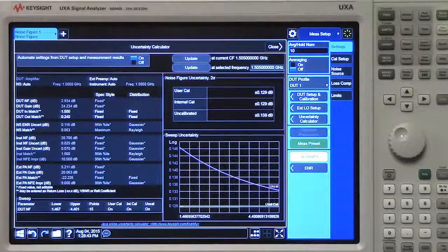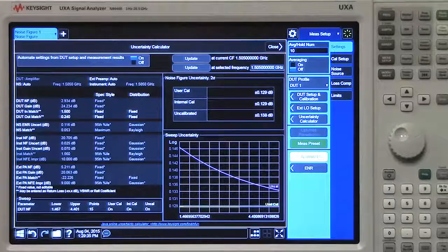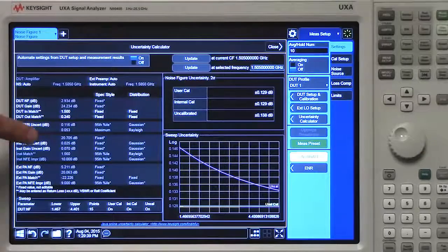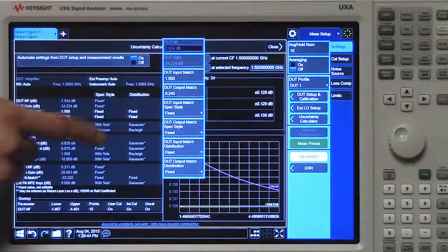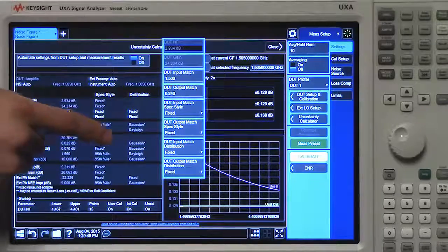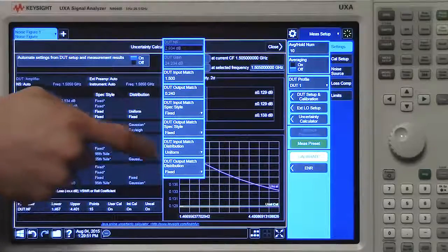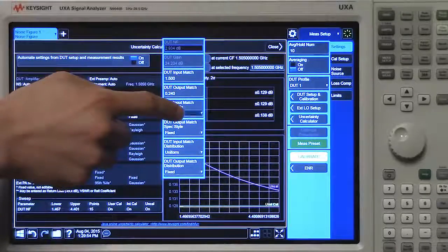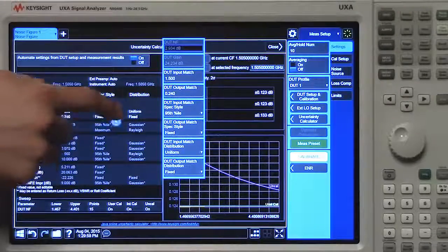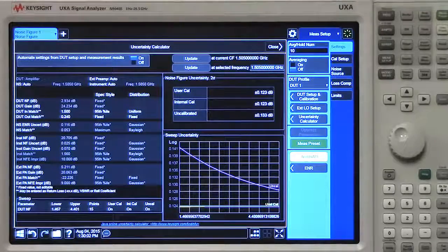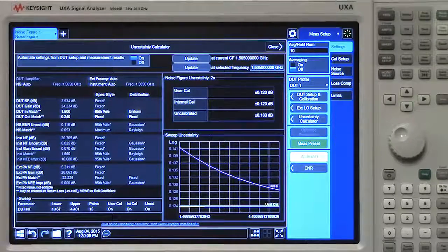Our competition, on the other hand, forces the user to manually enter these values. Also notice we give you full control over the distributions that model your DUT's input and output matches. We could change our input match distribution to a uniform distribution that is specced according to the 95th percentile, for instance. Now our uncertainty calculator has more information to go off of. This will give you a more accurate estimation of the measurement uncertainty.